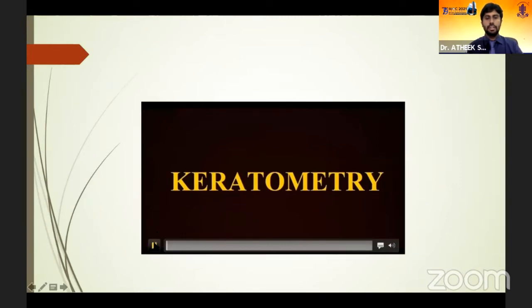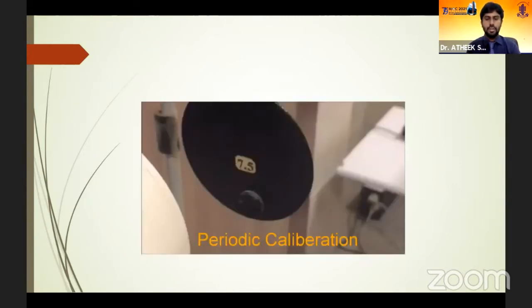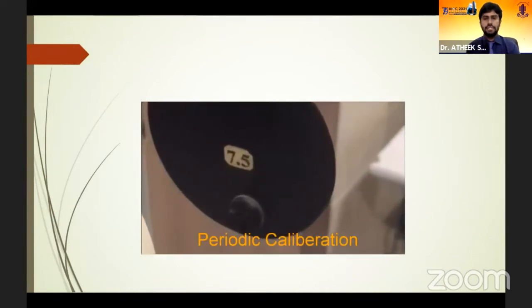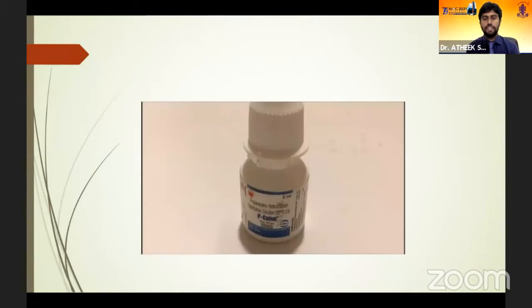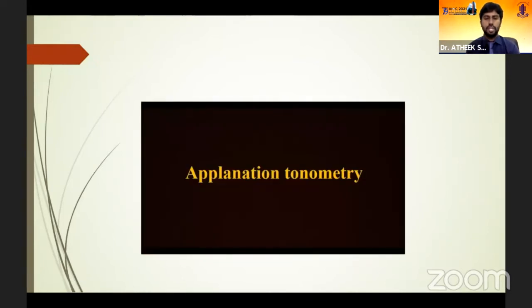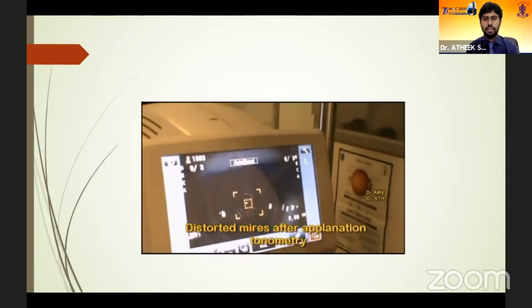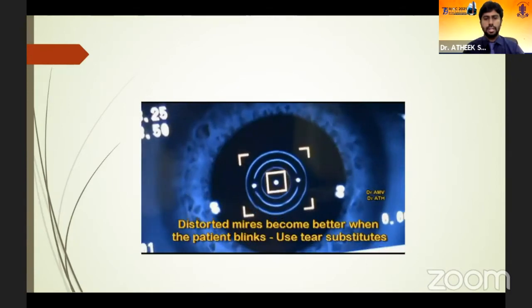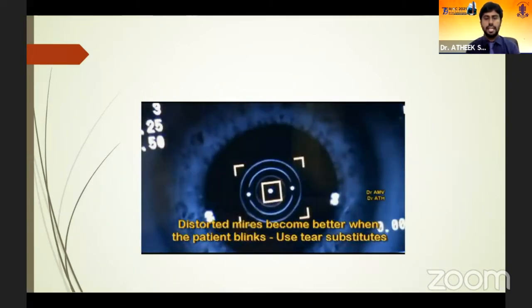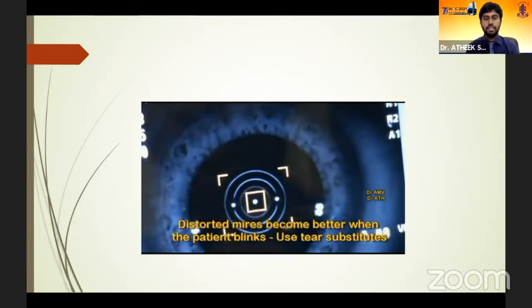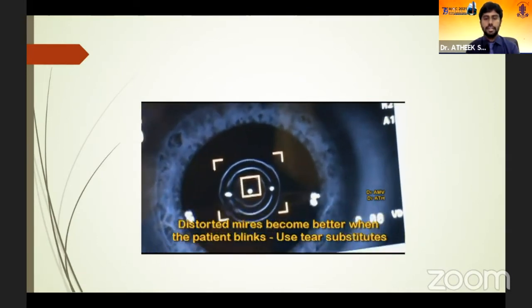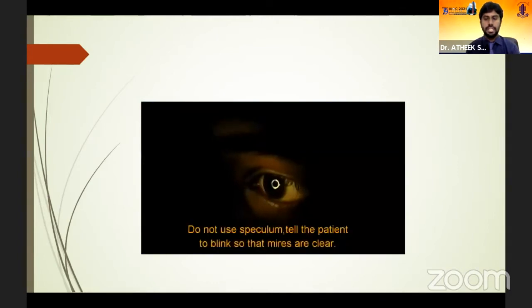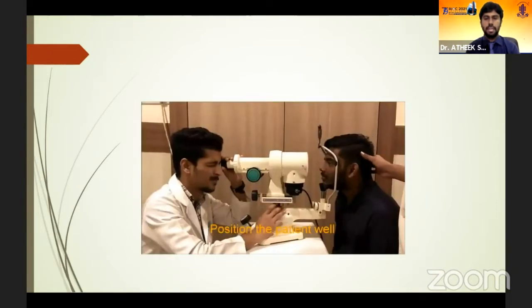Practical tips for manual keratometry: calibration is very important, and the user must adjust the eyepiece based on their refractive error. Always perform on a virgin eye — do not do it after applanation tonometry or after applying local anesthetics, which will disturb the cornea. Ensure that the tear film is proper before keratometry. Do not perform on a very dry eye. If you suspect dry eye, tell the patient to blink frequently, apply a drop of CMC, and then proceed.